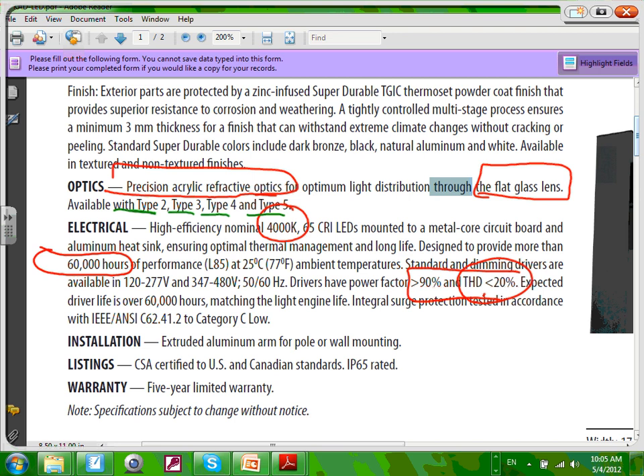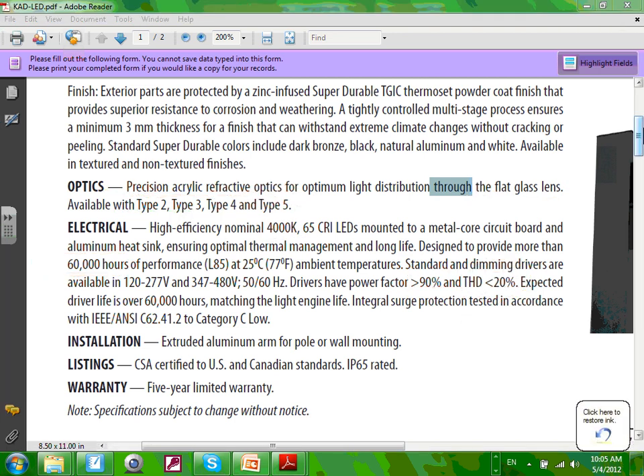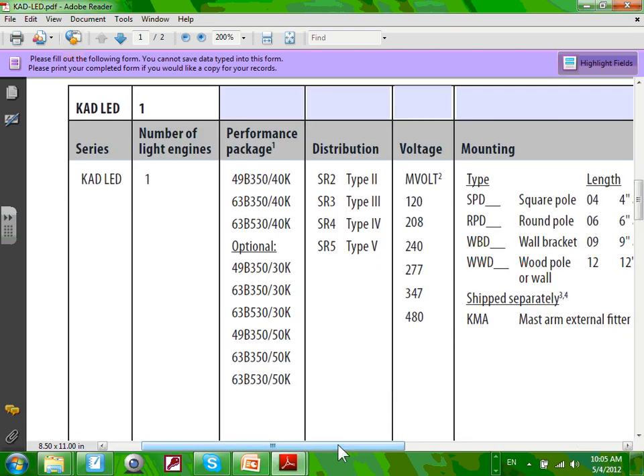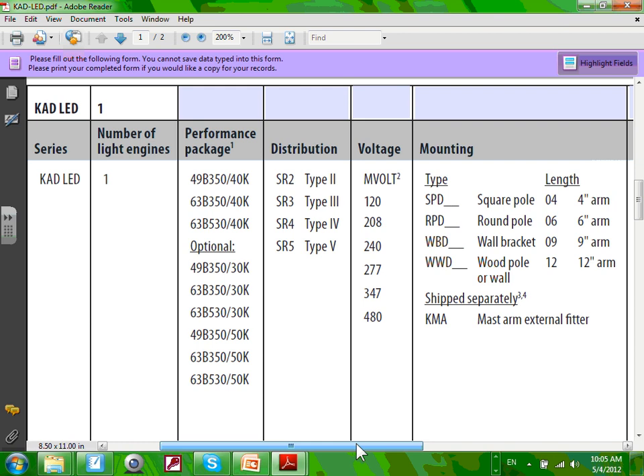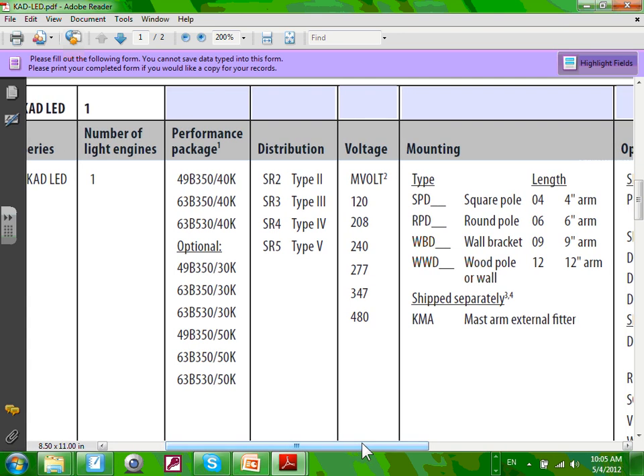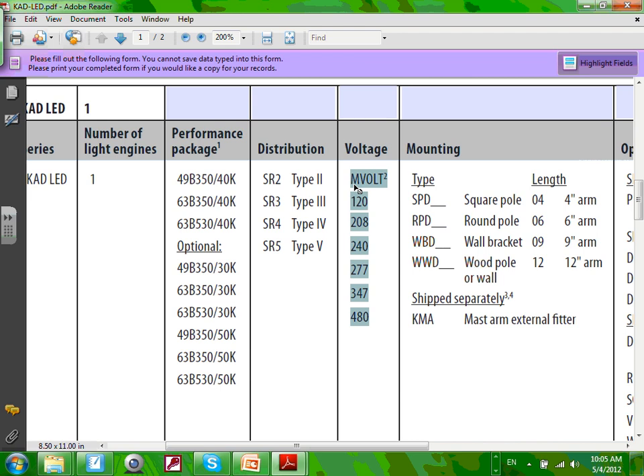These are the highlights from the fixture we chose for our project because we did the LEDs. Here's the KAD LED — it comes in a performance package with distribution patterns that can shoot forward, sideways, and all this good stuff we talked about. My favorite — you can burn this one on multi-voltage. You can pick multi-voltage and bring any voltage to this fixture, or you can specify a particular voltage. You can burn this one at 480 — two hots coming directly to it.